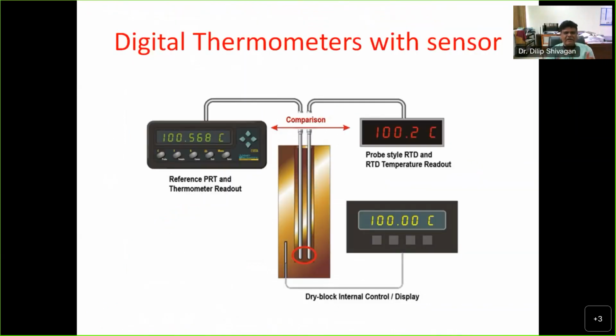So at your level, at the practical level, mostly digital thermometers with sensors are used. So there you have one as a reference and another as a device under calibration, and that is placed in a very highly stable dry block or water bath or some oil. Okay, and that needs to be very, very stable. So the zeroth law of thermodynamics is the application. Okay, you have set the furnace temperature. Now this oil or bath will start heating. It will be in thermal equilibrium. Then these two sensors will be in thermal equilibrium with the bath.